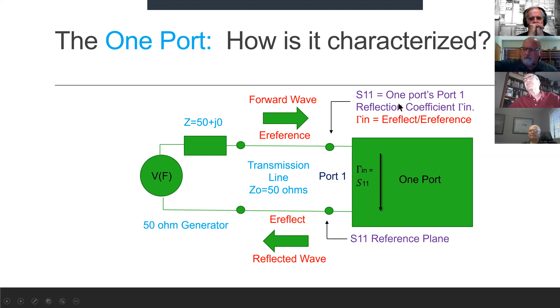Once again, the reflection coefficient, gamma, is E reflect divided by E reference. It's a complex quantity because E reflect and E reference have a phase difference between them, making this a complex polar number. It's measured in a 50 ohm system because the generator impedance and the transmission line impedance are 50 ohms. E reflect and E reference must be measured at the same point on the transmission line. This point is called a reference plane, and gamma may also be called S11.